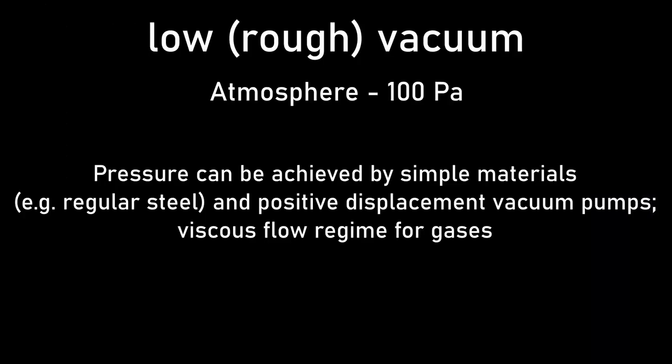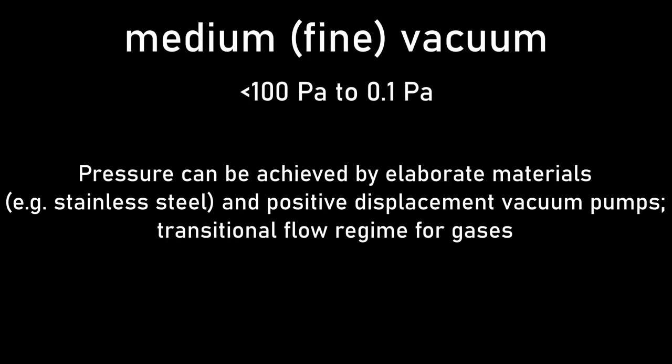Rough vacuum, also called low vacuum, covers the range from atmospheric pressure down to 100 pascals. At this pressure, gases still act like a fluid and exhibit viscous flow. Gases start to transition out of viscous flow in medium or so-called fine vacuum, which covers the range from 100 pascal down to a tenth of a pascal.